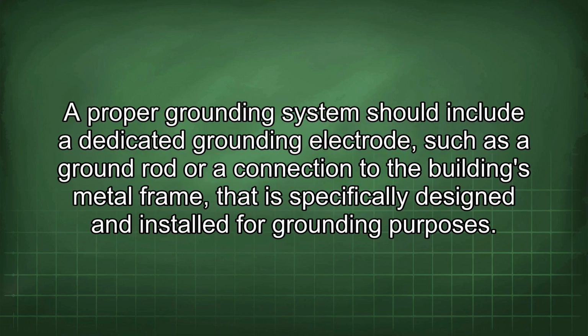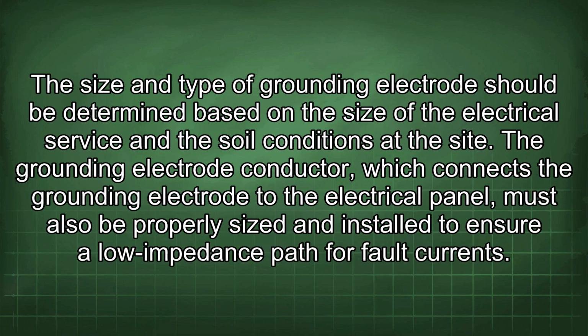A proper grounding system should include a dedicated grounding electrode, such as a ground rod or a connection to the building's metal frame, that is specifically designed and installed for grounding purposes. The size and type of grounding electrode should be determined based on the size of the electrical service and the soil conditions at the site. The grounding electrode conductor, which connects the grounding electrode to the electrical panel, must also be properly sized and installed to ensure a low impedance path for fault currents.